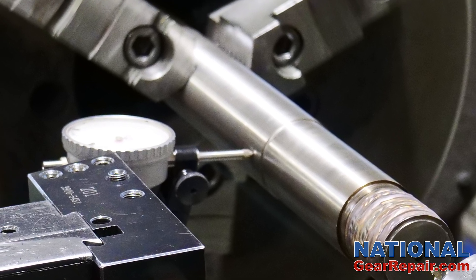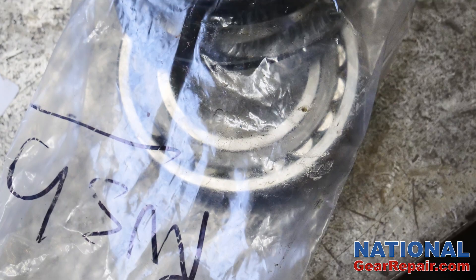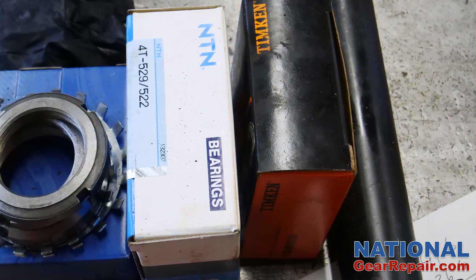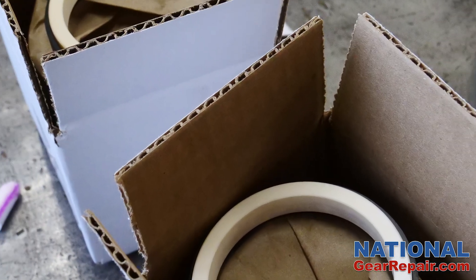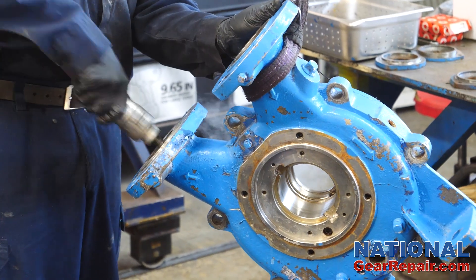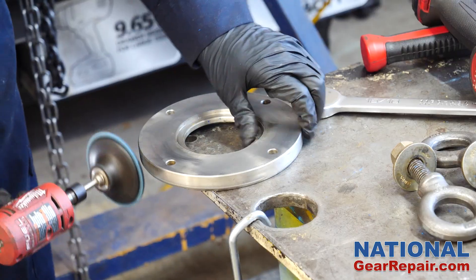The shafts were checked and found to be within OEM specifications. All new bearings, seals, gaskets, and mechanical seals were ordered. All of the ports, mating surfaces, bearing bores, and cover plates were cleaned and polished.